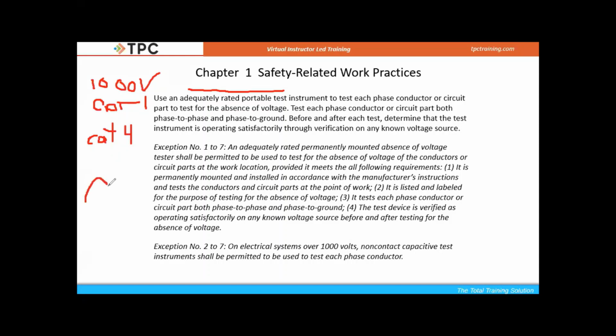And those categories are protecting us from this. If I have my sine wave, and then on top of my sine wave, I might see something like this, which we're going to call a transient or a spike, then these meters can only withstand so high of a voltage. For example, a category 4 meter can withstand up to an 8,000 volt spike without being destroyed. A category 1 meter is going to be as low as a 2,500 volt spike. So we have to have the right meter in our hand when we do this, because if these transients are present, they can destroy our meter.